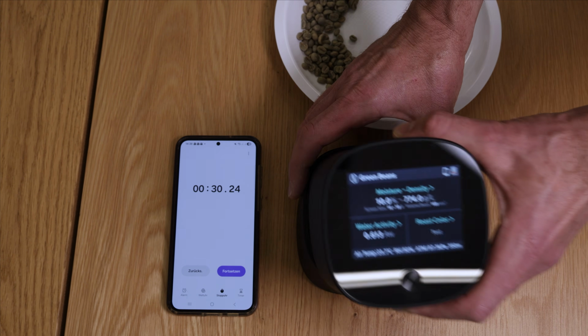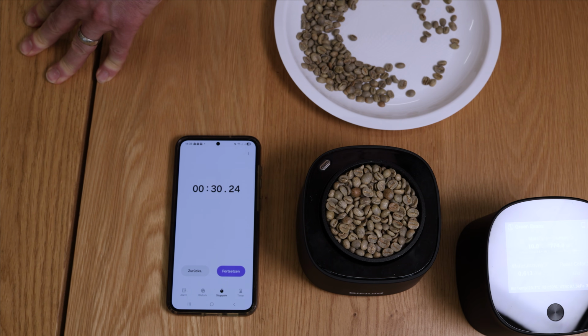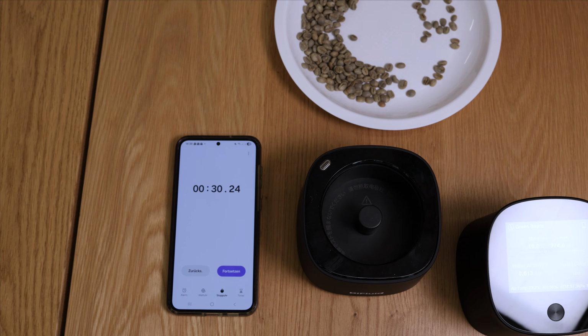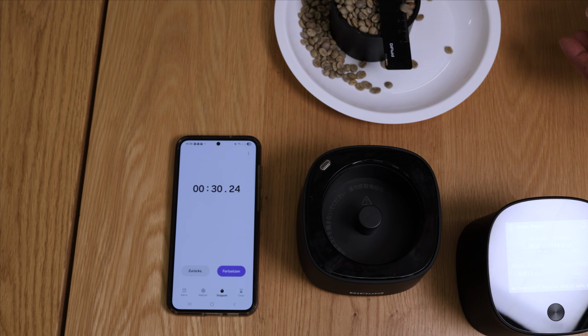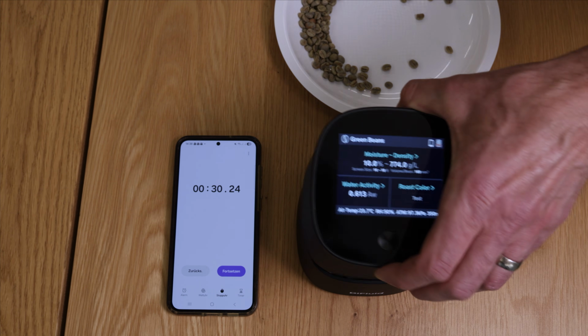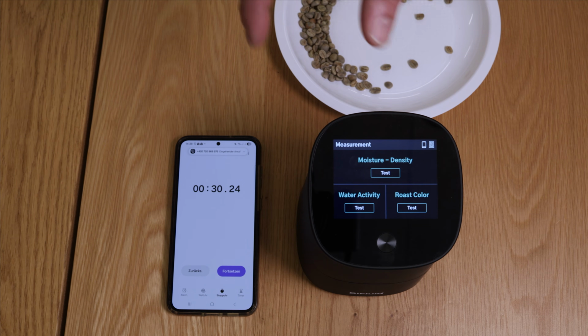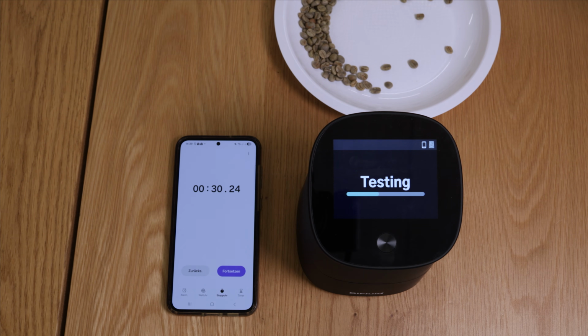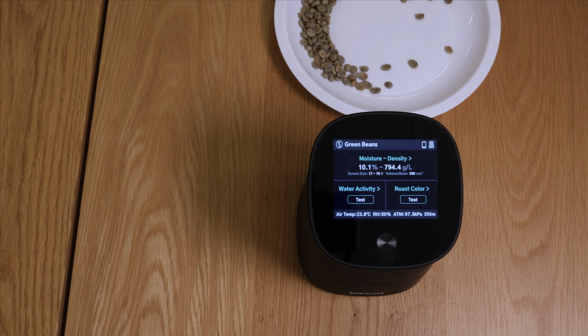We can actually do another sample just in order to make sure that we get consistent results. So I'm preparing the sample again. Go again to measurement, moisture and density, 10.1% moisture content, water activity. So you see the measured water activity is 0.618. So all in all, the measurements within this device are quite consistent, and this is the way you're measuring moisture, density and water activity with the DiFluid OMIX Plus.